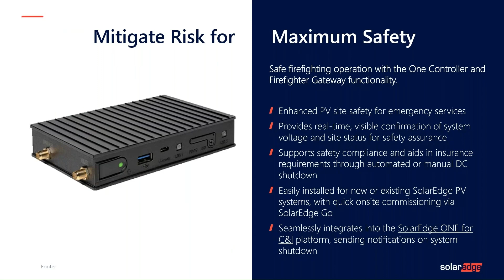And then what would happen if the fire alarm or the emergency stop was pressed? The signal will be sent to the inverters to say shut down. The inverters would then depower the optimizers by ramping down production, as you can see here, and going to safe DC. So it's not just turning the inverters off.